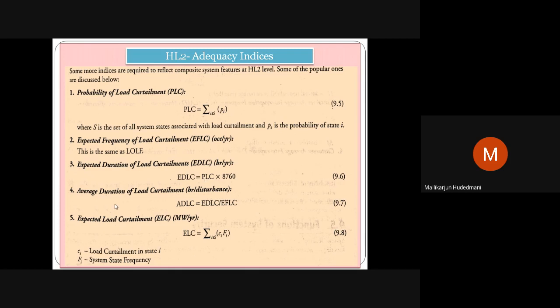Next is average duration of load curtailment, ADLC, counted per disturbance or per curtailment or disconnection—how many hours. ADLC refers to total curtailment, EDLC (PLC into 8760) divided by frequency, EFLC, giving how many hours are allocated per disturbance. These are parameters similar to HL1, but here both generation and transmission are considered jointly. So ADLC equals EDLC over EFLC. One needs to practice these keywords carefully because they look and sound very alike, though their presentation under HL1 and HL2 differs.